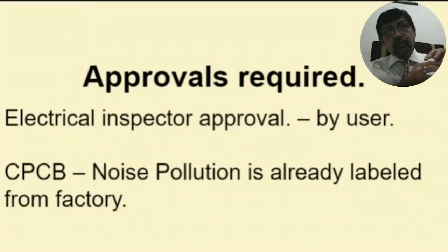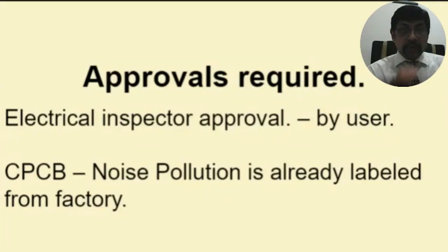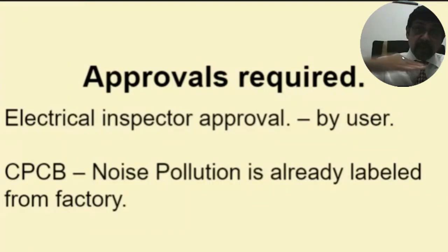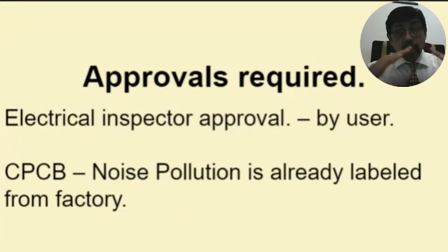Now, suppose in case of automatic, where we have an auto changeover system or an auto AMF panel, that is auto mains failure panel. Now, the load is running on mains power, and the mains power fails, and the AMF panel gives a command to the generator to start, and the generator takes over the load. Now the load is running on the generator, and suddenly the mains power comes in again. Now to ensure that these two powers do not collide, they do not mix and create a disaster, there has to be an isolation given. An isolator or locking between the two outgoings has to be given. Now that is checked by the electrical inspector, that when the generator is running and the mains power comes in, there is proper isolation between the two powers, so they do not mix and create any untoward happening. So that is what the electrical inspector takes care of.